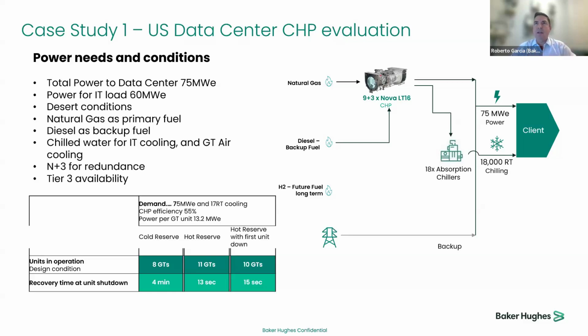In this specific location, the grid can provide backup power, not for the full capacity of the data center, but for a good estimated portion. So in this case, cogeneration will generate 100% of the electricity for the data center, and with absorption chillers, it will provide chilled water - around 18,000 RTs - used for IT cooling and also gas turbine air cooling.